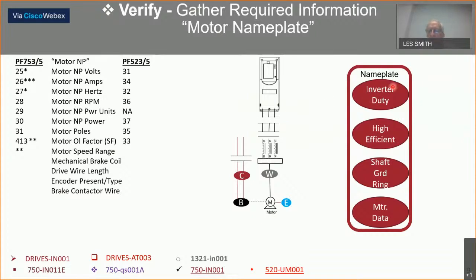Look at your motor nameplate. It's going to say if it's inverter duty, high efficient. That's important on tuning. Shaft ground rings. Certain horsepowers, you're going to get some ground rings by default in there for common mode noise, which is nice to know. And then the motor data itself.